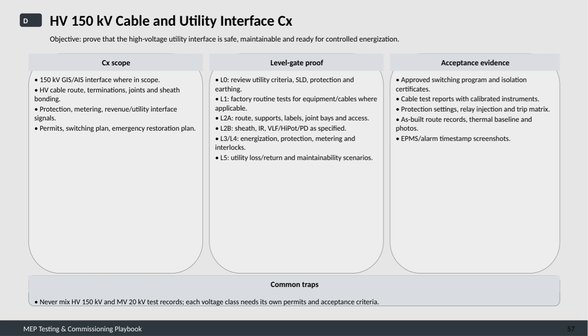joints, and sheath bonding. It also covers protection systems, metering, and utility interface signals, as well as relevant permits, switching plans, and emergency restoration plans. Next, the level gate proof outlines specific stages of verification. At level 0, we review utility criteria, single-line diagrams, protection, and earthing. Level 1 involves factory routine tests for equipment and cables.